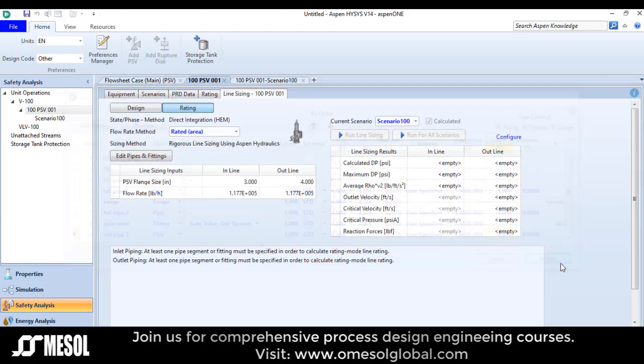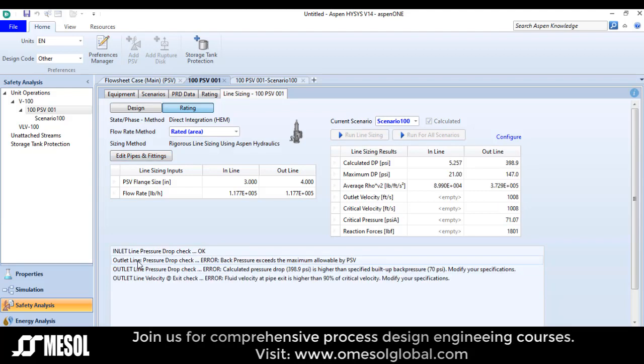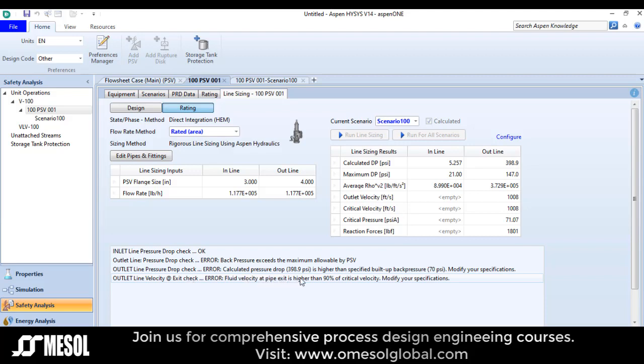Now I will click the accept button and click 'run line sizing'. The outlet line pressure drop check gives an error: back pressure exceeds the maximum allowable by the PSV. The calculated pressure drop is higher than the specified build-up back pressure of 70 PSI, and there is also an error regarding exit velocity: fluid velocity at the pipe exit is higher than 90% of the critical velocity. So we need to make some changes.